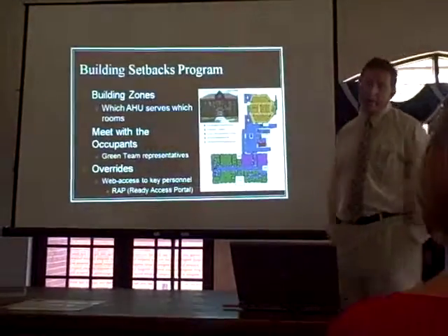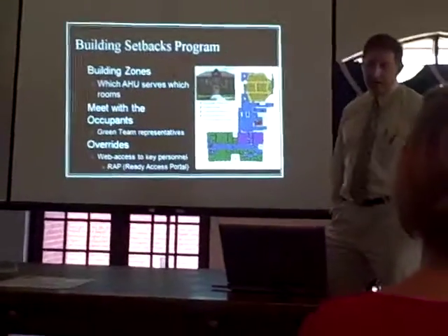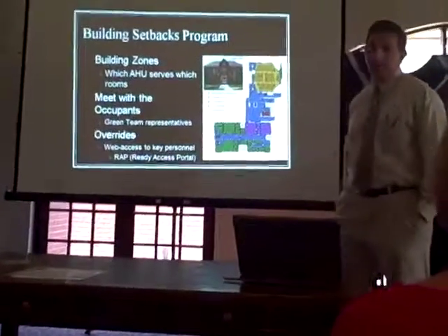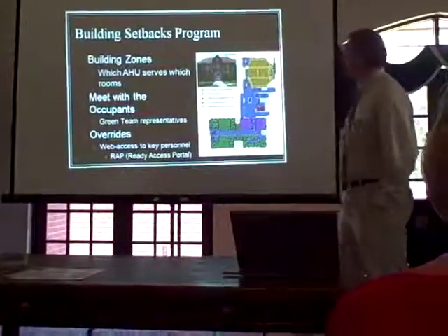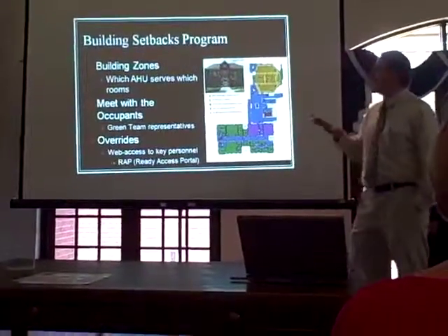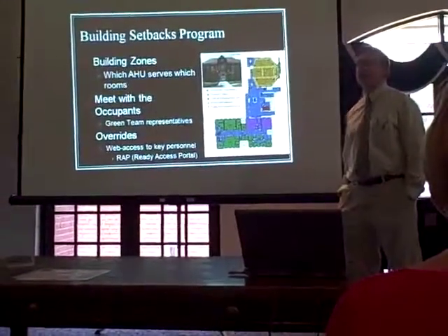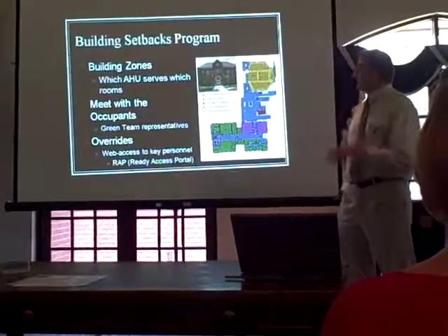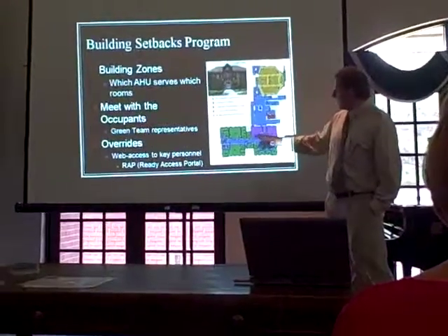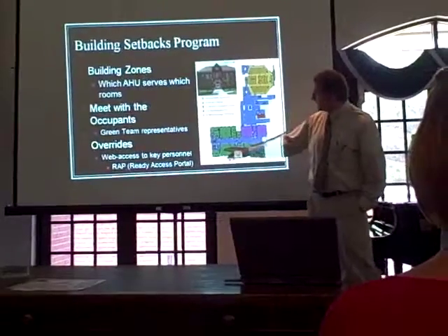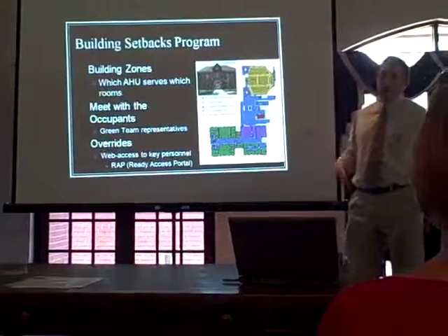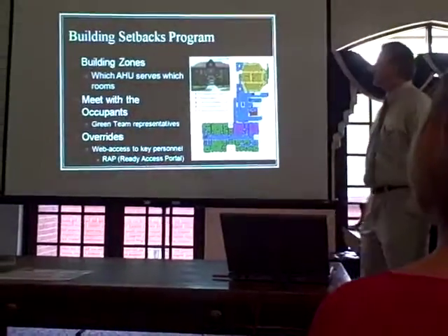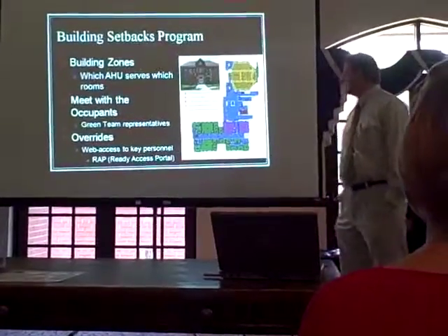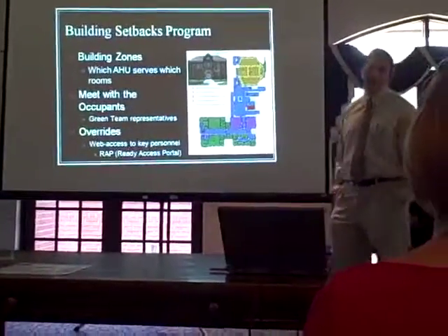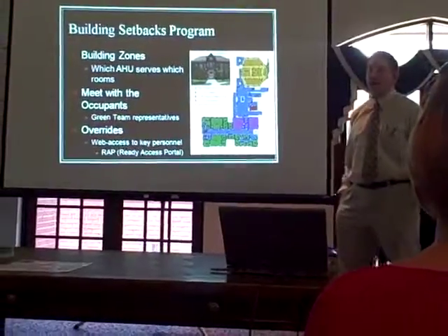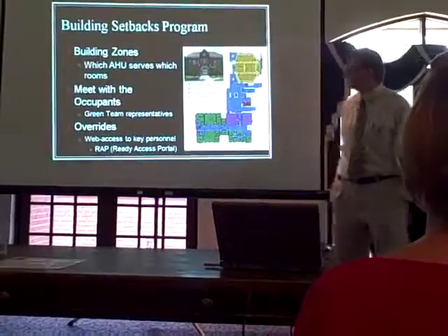Building setback program. What we're trying to do is identify all the zones that the air handlers serve, what rooms are served by which air handler. The idea is so that we can schedule this building but not this building. If these are just offices, we can schedule it, or for whatever the classroom or whatever the function of that space is. And in doing so, we can save a tremendous amount of energy in terms of not having to run that air handler unit or the area that it serves.